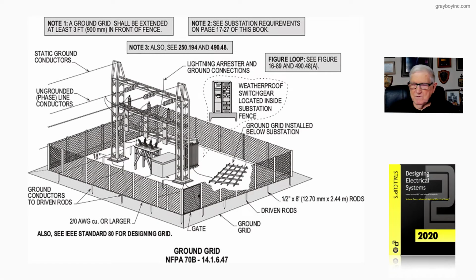Now let's look at this figure 17-37 that deals with a customer-owned substation. Now you see that you have the utility power coming in. Then you see you have a weatherproof switchgear located inside the substation fence, and that's the service point for this facility in accordance with the definition of service point from Article 100.